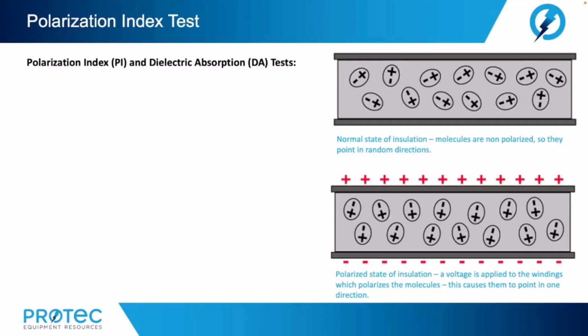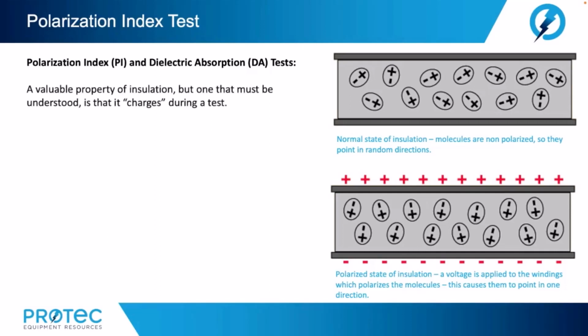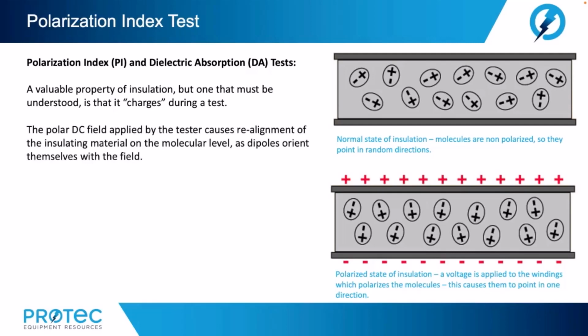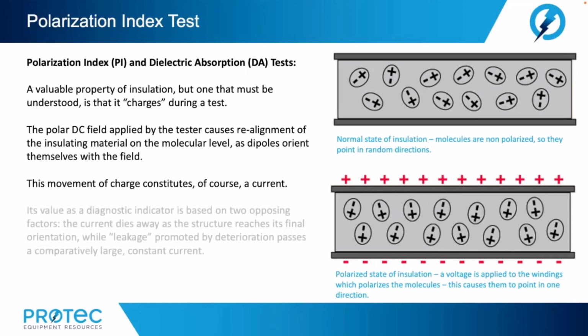All right, let's look at polarization index tests. Polarization index and dielectric absorption tests. Now, a valuable property of insulation, but one that must be understood, is that it charges during a test. The polar DC field that's applied by the tester causes realignment of the insulating material on the molecular level as dipoles orient themselves with the field.